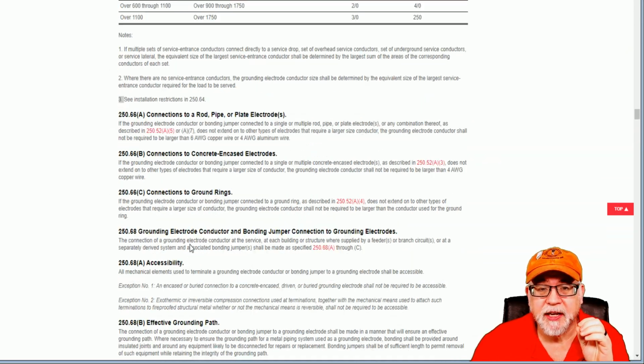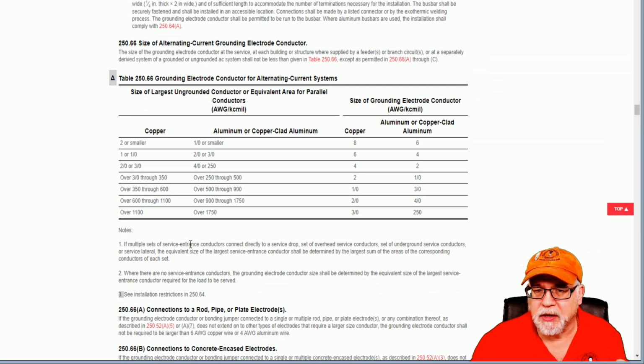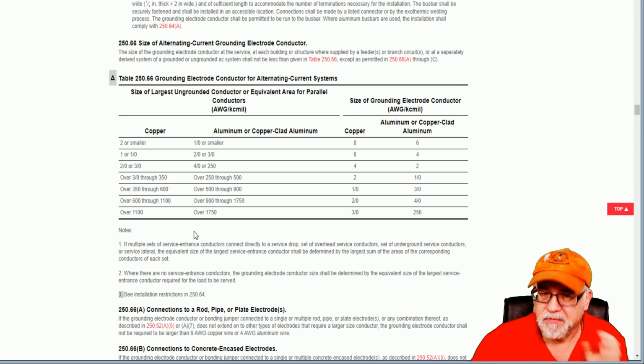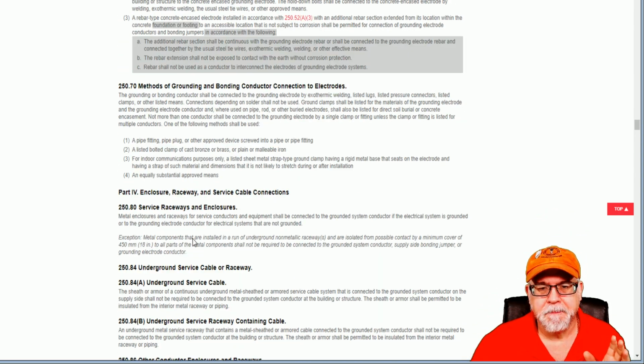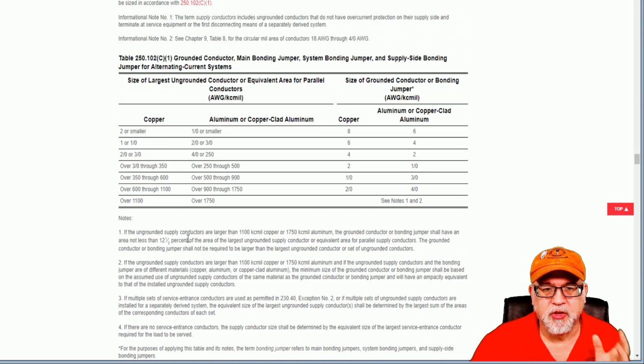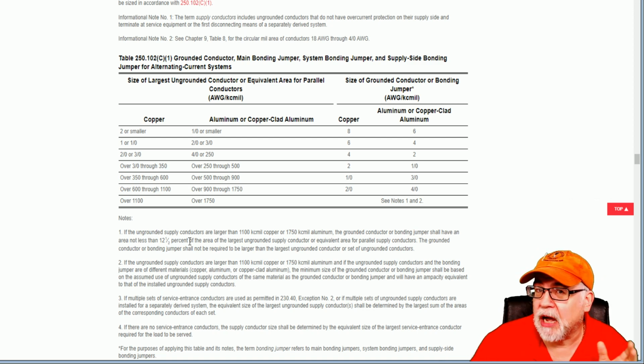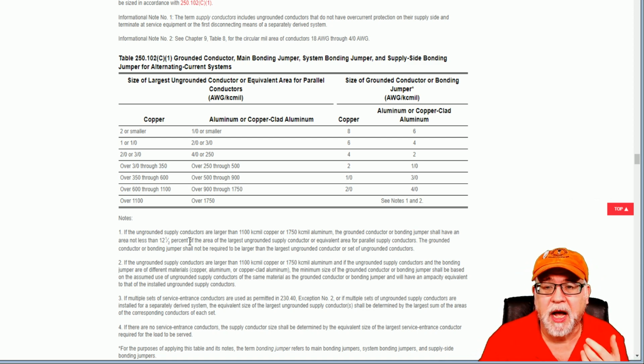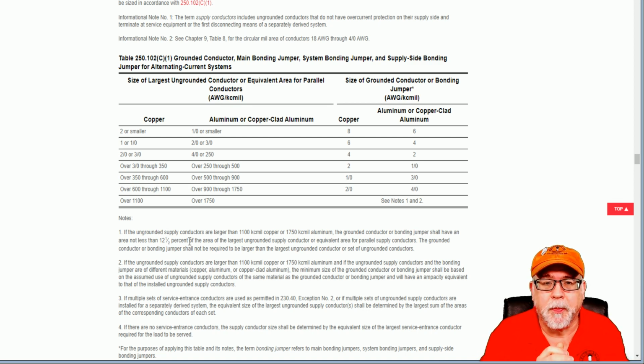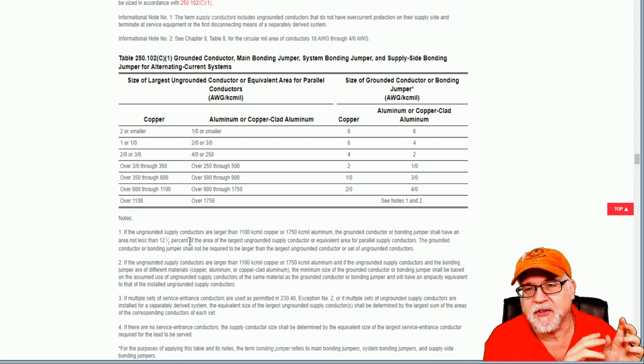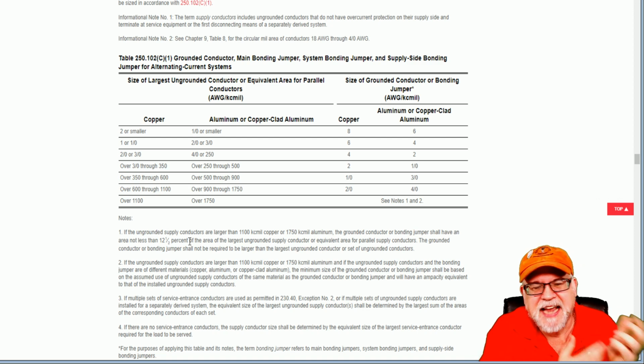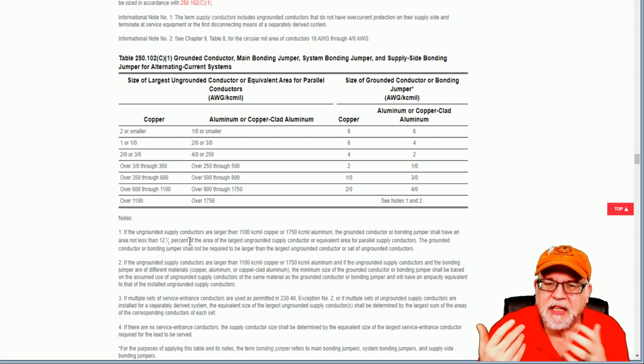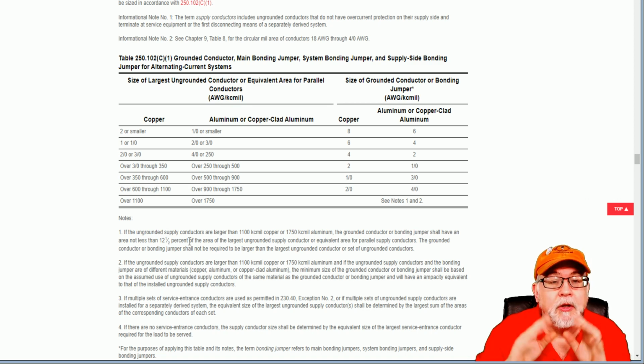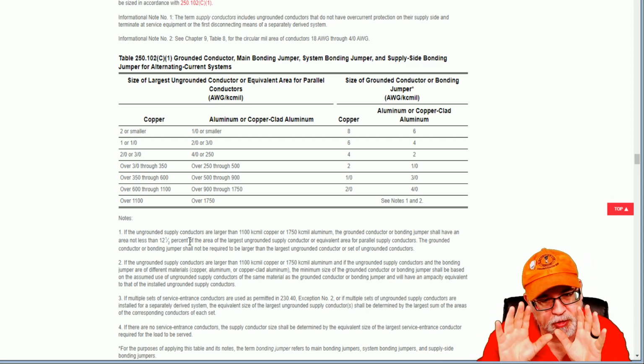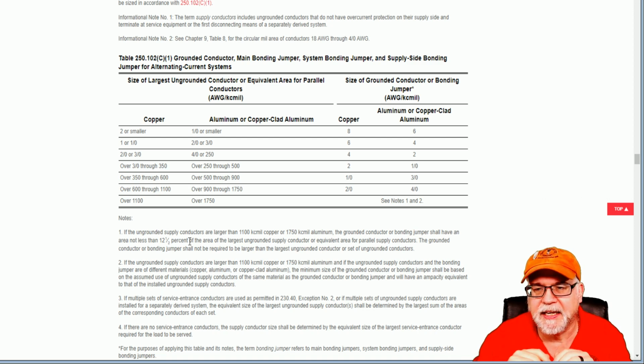Oh, incidentally, don't get confused, because 250.66 is dealing with grounding electrode conductors, okay? That's what that's all about, so not where we want to be. And you go down and you'll see there's a 250.102(C)(1). That's also not where we want to be, because that's dealing with the grounded conductor, main bonding jumpers, system bonding jumpers, supply-side bonding jumper. Great table. It came to us 2 cycles ago. We used to refer you back to 250.66, which was a bit misleading, because that table was for grounding electrode conductors, yet we were sending you there for grounded conductors and bonding jumpers. A couple cycles ago, they created table 250.102(C)(1). It gives you guidance now.